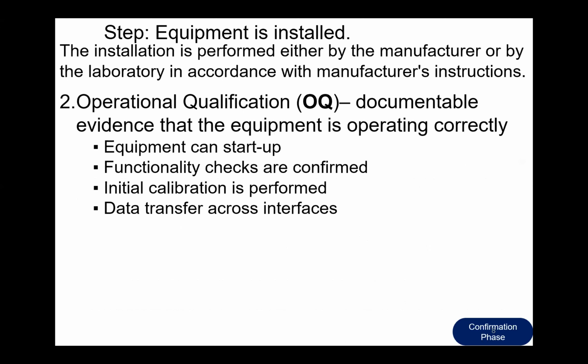So there should be evidence that the equipment can start up, all the functionality checks are confirmed, initial calibration is performed, and data transfers across interfaces. Like I mentioned, before an installation engineer leaves, there should be evidence that the equipment is working. Don't leave it to the next day before you know that the equipment is working. In good lab practice, the lab and the engineer sign off that the equipment is ready and working.